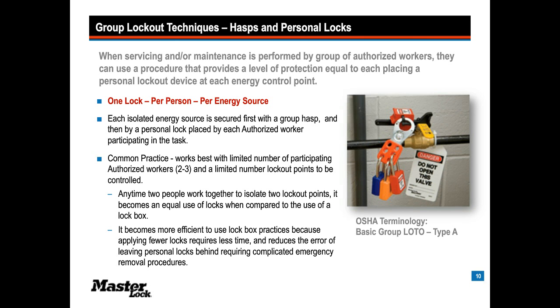and if my lock went directly into that device and there's only room for one lock, we've got some decisions to make here. And the right decision is, let's take off my lock, let's put a hasp on, let's put my lock back on, and have anybody joining me add their lock into this hasp type operation.